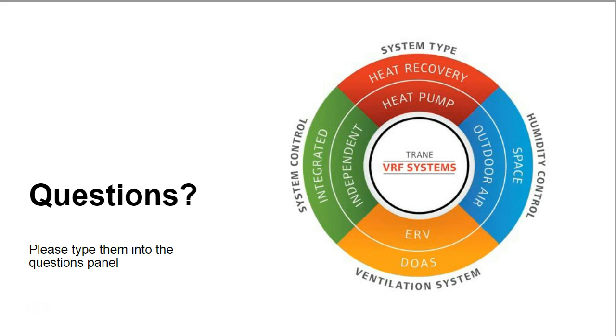One thing that I like is that some manufacturers' branch controllers can handle more than one VRF terminal zone unit on one branch. The caveat of this is that all the units on that one branch will operate in the same mode. So you can have a heat recovery system, but if you have multiple units on one branch port, they're going to be limited to a heat pump application, which means all the units on that port are going to be either heating or cooling. Right now, Mitsubishi has the largest 16-port branch controllers, and each one of those ports can handle up to 54,000 BTUs per port.